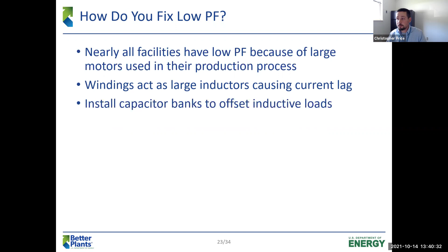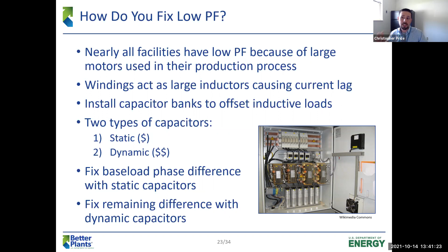There is static capacitance, which is cheaper, and dynamic capacitance, which is more expensive. The static capacitance is going to provide a constant amount of capacitance. The dynamic systems have electronics in them that let them vary the amount of capacitance that your plant has to fine tune what that adjustment is. So you would fix a base load amount of power factor with that static capacitance, and then fix the remaining with the dynamic. And that way you minimize the cost. And typically, if you look at the IAC, the Industrial Assessment Center database, paybacks on fixing power factor are usually around a year to a year and a half. They're almost entirely under 2 years.